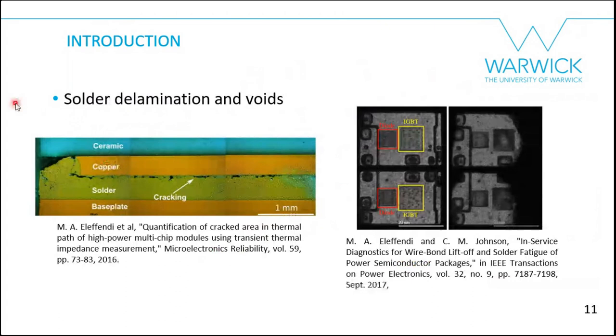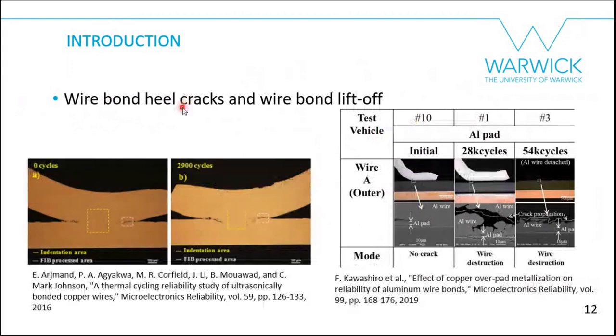Regarding solder, the failure mechanisms are solder delamination and voids. You can see cracks on the DBC-to-base-plate solder attachment in figures, and using scanning acoustic microscopy or X-ray you can also see voids on the substrate and in the solder below the chips. For wire bonds, the typical failure mechanisms are heel cracks and wire bond lift-off.